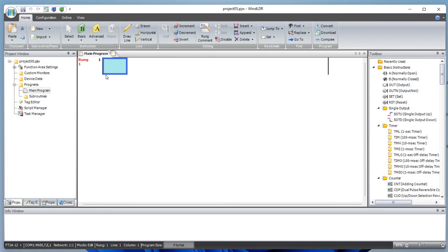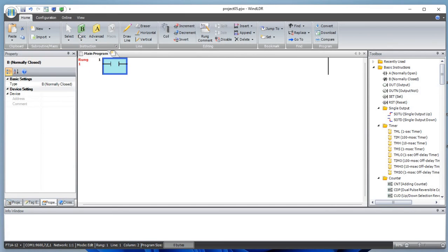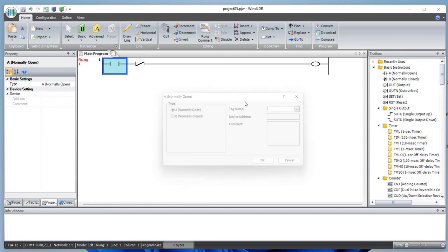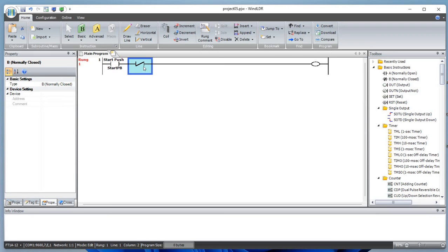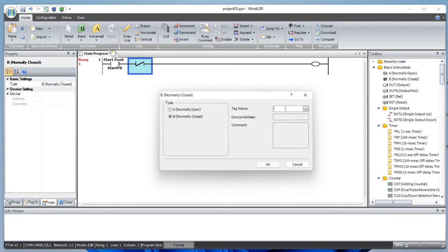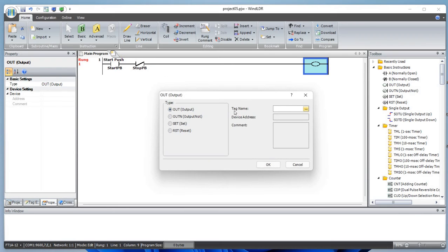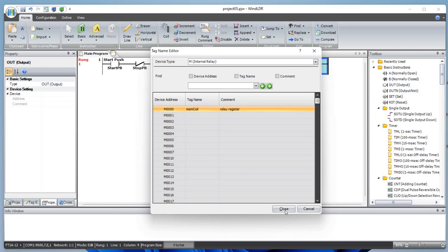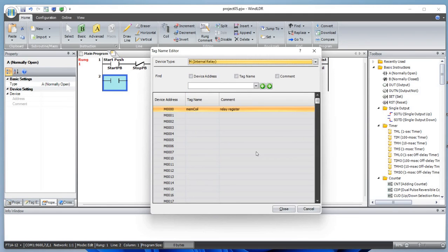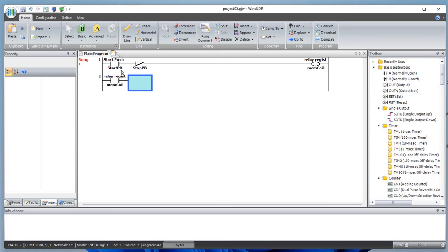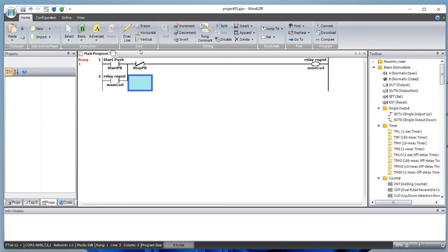Let's add a simple normally open contact, normally close contact, and an output coil. Based on our input/output definition, we can connect those to the coil — start push button and this will be our stop push button. This will turn on the memory coil or memory register. Let's add a normally open contact which will be our memory bit, and let's draw a line to complete the rung.